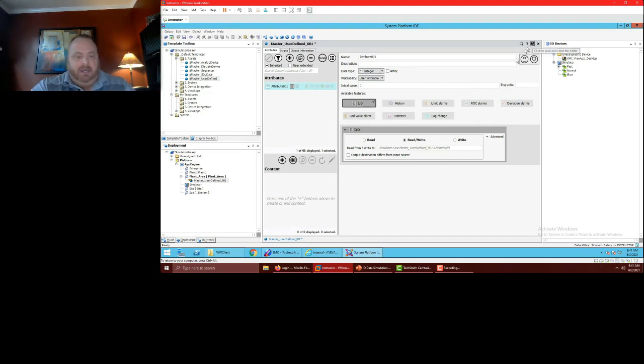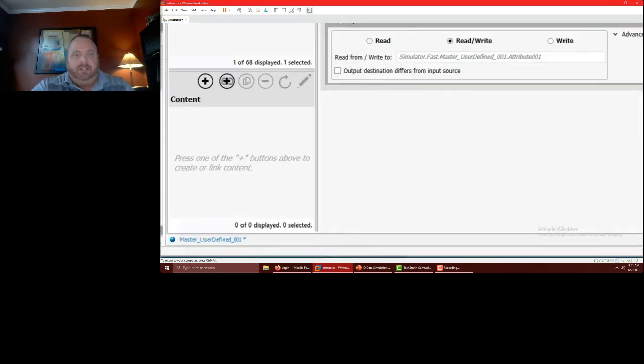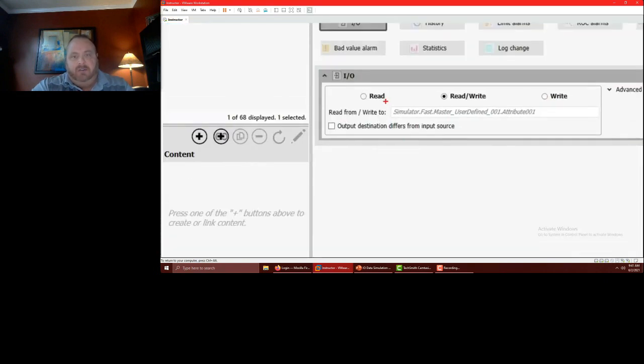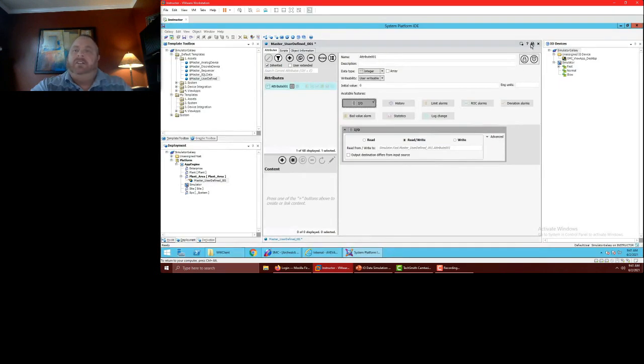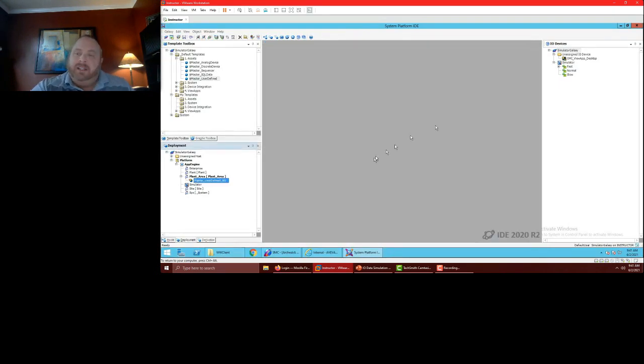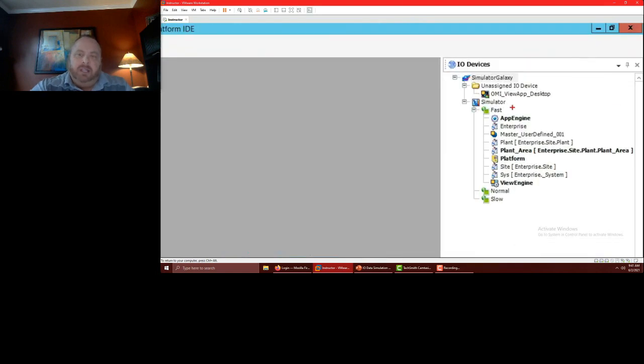And so what we're talking about here is you've got to fill in what the I/O address is if you're not using auto binding I/O, right? So this is doing it for me just because it's specified a default. But if I didn't do that, it's literally just as simple as dragging and dropping over here into my I/O devices group the object into the appropriate scan group that gets defined in this OPC client object here.